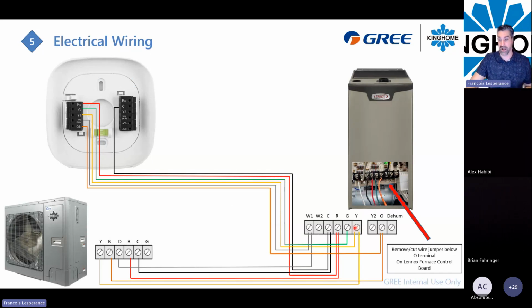But on a furnace, yes, you have one, and you will need to connect it to make sure the system applies the right speed, because you have a coil to use with the heat pump. Even if it's a cooling call or a heating call, you will use the same amount of CFM through that coil, because you need to provide the same capacity through that coil in cooling or heating mode. So with the furnace, you will hook the Y terminal right here, just to tell the system that you have a call for the compressor.